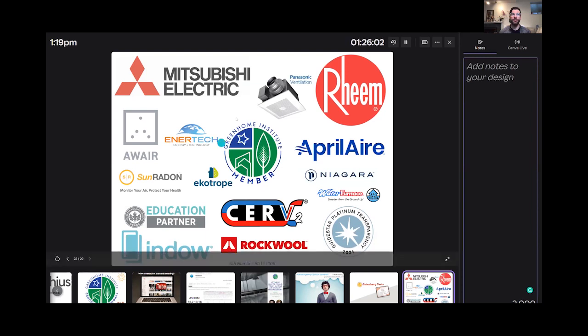We play at the level of the whole home. When there's a particular room, like often a bedroom, there's concerns, CO2 is going to be high during the nighttime. Maybe you have a nursery, so you just care more about that room than other rooms. If you have a particular room of concern, there is an application for other products that detect and solve problems on a room basis. You can get a HEPA filter air purifier in a room connected to an air monitor. That's a great solution for a room. We're not saying anything negative or bad about that, but where we play is at the whole home level. So if you have whole home equipment, we want to know what's happening as an average across all the different areas of the home that are being controlled by that piece of equipment.